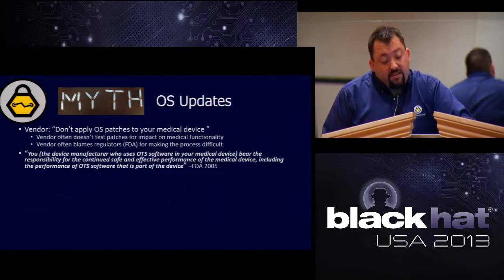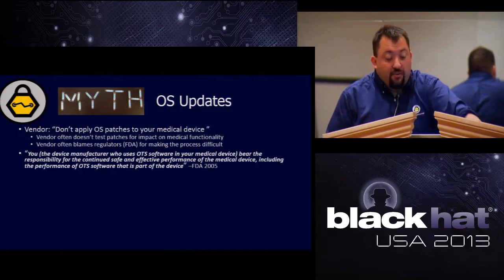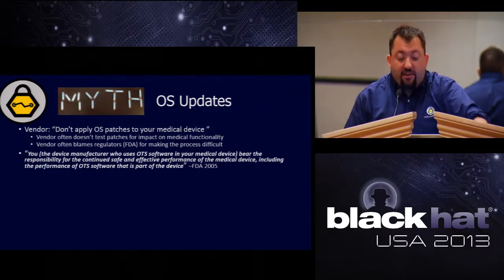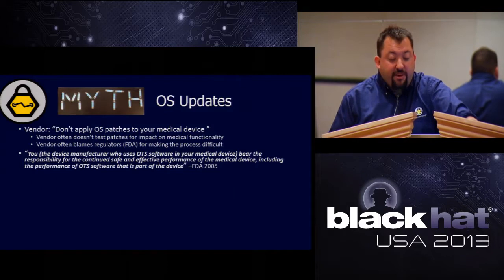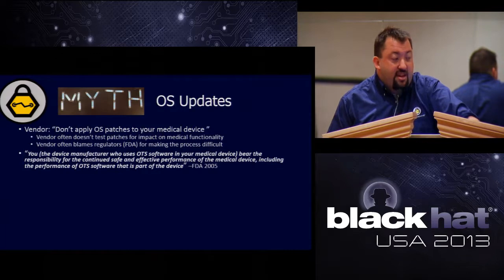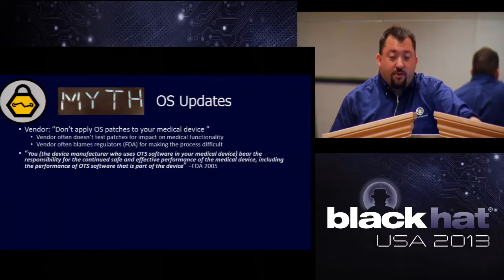The FDA statement on this in their guidance documents is that you, the device manufacturer who uses off-the-shelf software in your medical device, bear the responsibility for the continued safe and effective performance of the medical device, including the performance of the off-the-shelf software that is part of the device. The vendor is responsible for those patches, for making sure their device works with those patches, by law, says the FDA.